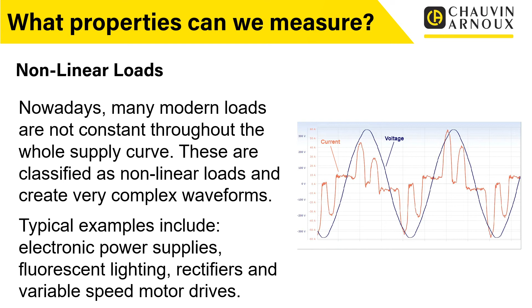These complex waveforms can cause a wide variety of issues within the installation, especially if they combine. You can imagine one little power supply isn't much of a difficulty, but if we've got loads of them in an office, or loads of motor drives in a factory, the combined effect can have a big impact on the waveforms. A common example is overheating of electrical distribution equipment, cables, transformers, motors, standby generators, and other components.